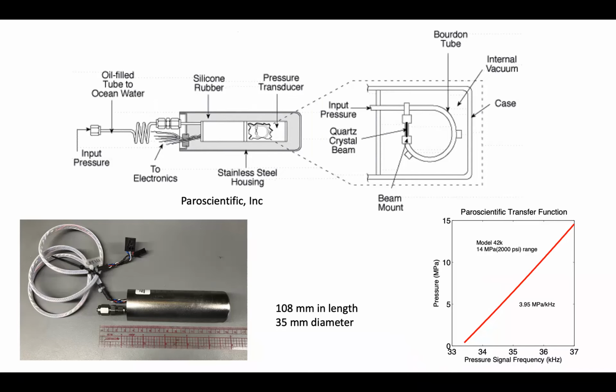When the crystal is excited, it has a resonant frequency of somewhere around 30 kilohertz, more or less. As the Bourdon tube is pressurized, it adds stress to the end of the tube, stretching or contracting the crystal, and the stress changes the output resonant frequency. In this particular case, it's about 4 megapascals per kilohertz, the transfer function for this type of gauge.